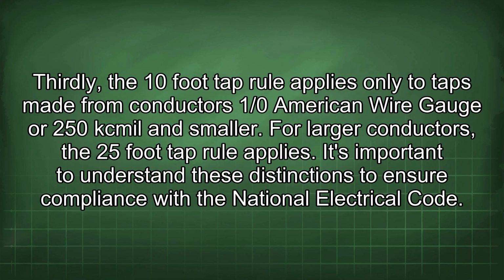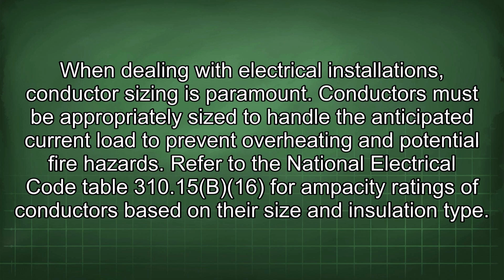Thirdly, the 10-foot tap rule applies only to taps made from conductors 1/0 American wire gauge or 250 kcmil and smaller. For larger conductors, the 25-foot tap rule applies. It's important to understand these distinctions to ensure compliance with the National Electrical Code. When dealing with electrical installations, conductor sizing is paramount. Conductors must be appropriately sized to handle the anticipated current load to prevent overheating and potential fire hazards. Refer to the National Electrical Code Table 310.15(B)(16) for ampacity ratings of conductors based on their size and insulation type.